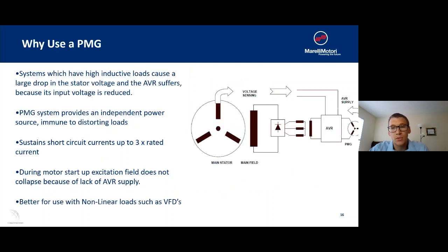So why would we use a PMG? A PMG is used when a system has high inductive loads that cause large drops in the stator voltage. This makes the AVR suffer because its input voltage is reduced. So the PMG system in this scenario provides an independent power source which is immune to these distorting loads. It helps to sustain short circuit currents up to two times, up to three times the rated current. And during motor starting, the excitation field does not collapse due to the lack of AVR supply. So it helps you start larger motors. It's also better for use with non-linear loads such as VFDs.